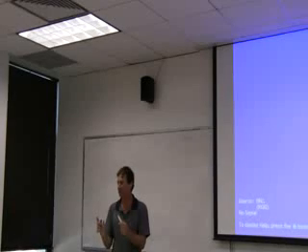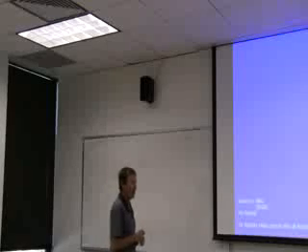The important part of this was the pressure sensor and the flow gauge were after the flow meter, which is a turbine type. And there's a big pressure drop across that flow meter. So that was appropriate. We wanted to check on that. We looked at calculating pressure and flow from the pressure transducer.